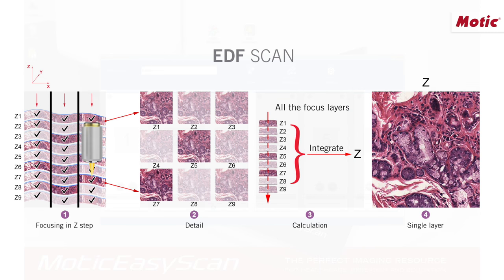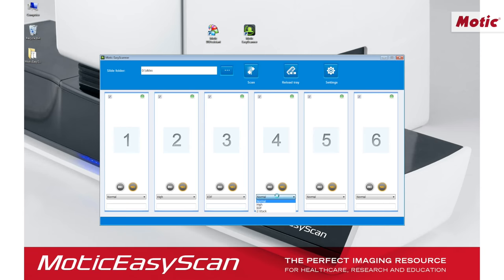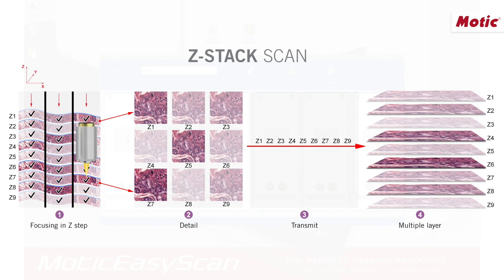Then we have EDF, extended depth of field. On this option, the system goes through several focal planes as previously, but in this case the different captures are combined into a unique image. Finally, we have the Z-Stack mode. This mode uses several focal planes as well, but in this case no further combination occurs, which means we will have a digital file that gives us image information about the different layers.